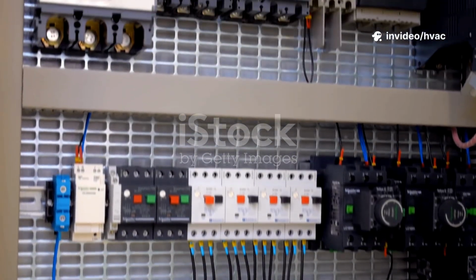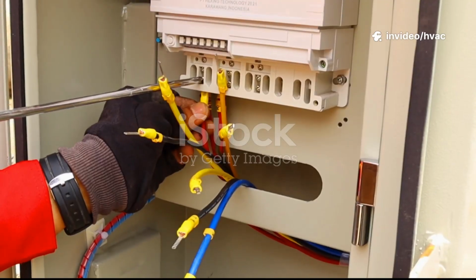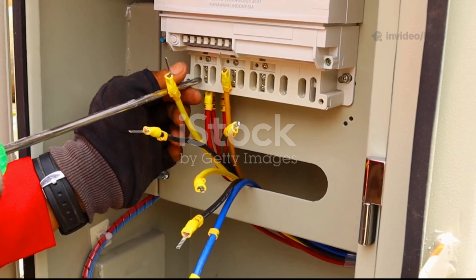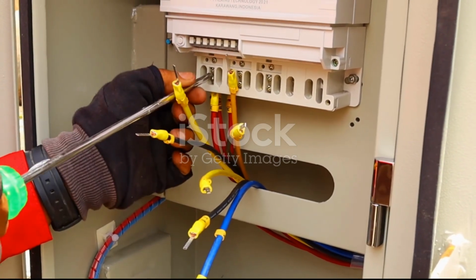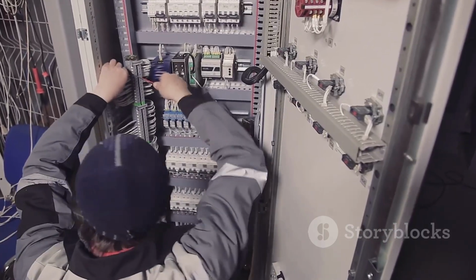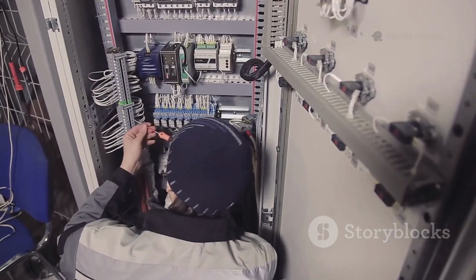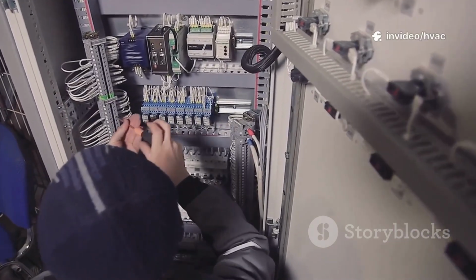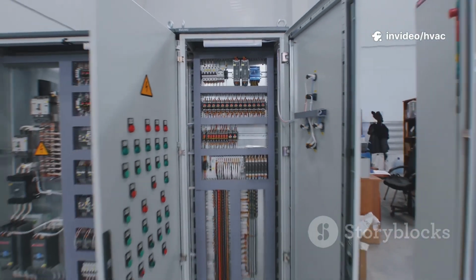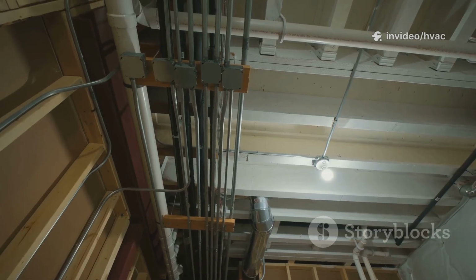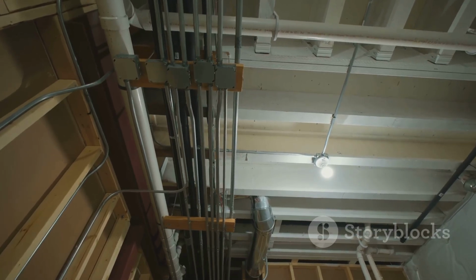How do interlocks work? Relays are the key. A relay is an electrically operated switch, letting low-voltage signals control high-voltage circuits safely. The relay acts as a middleman. The BAS sends a signal, the relay closes, and the motor starts. In interlocks, relays enforce the logic. A flow switch wired in series with a relay coil means no flow, no start.